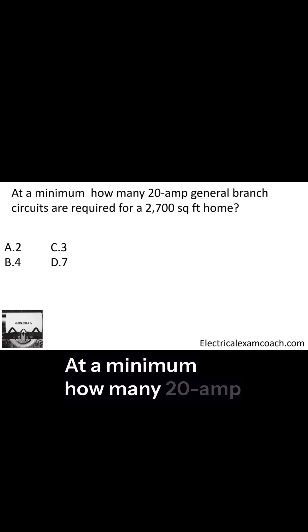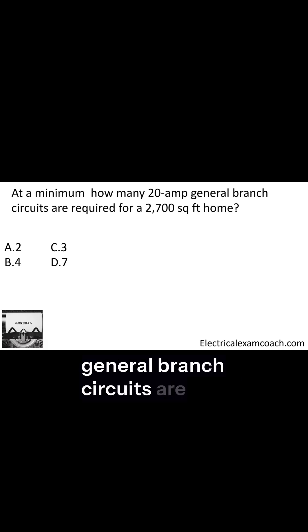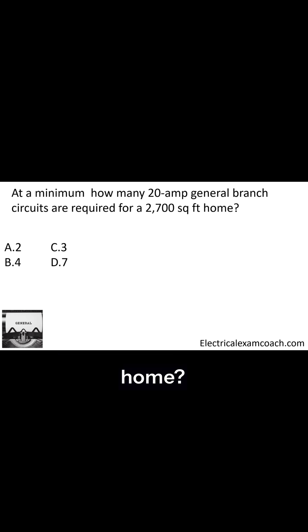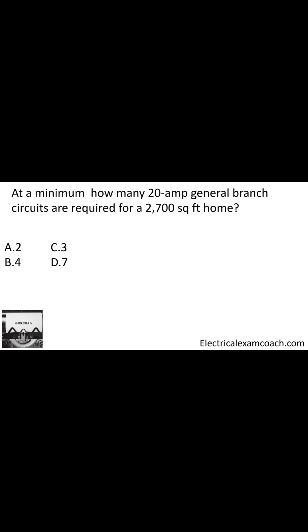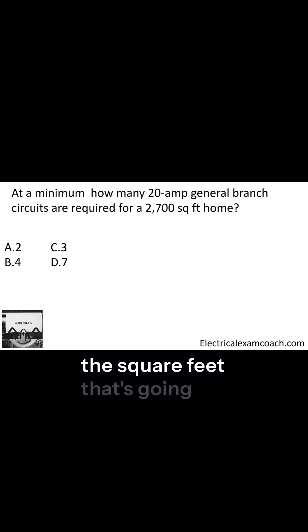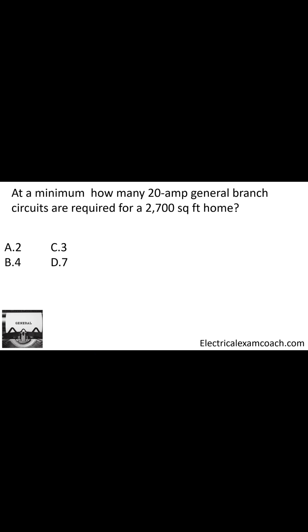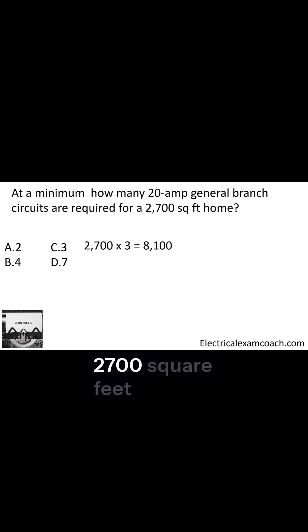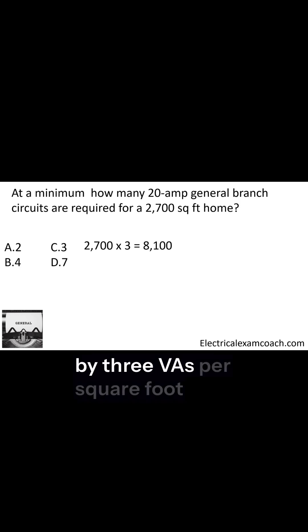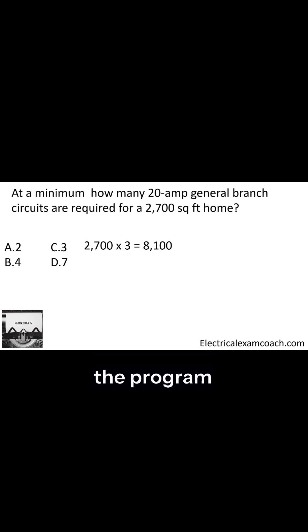At a minimum, how many 20 amp general branch circuits are required for a 2700 square foot home? Your question may not say 'general' — it may say 'for lighting and receptacles,' keep an eye out for that. But usually if they give you the square feet, that's the red flag that you're calculating the general branch circuits. The first step is to take our 2700 square feet and multiply it by three VAs per square foot, like we've learned previously in the program.